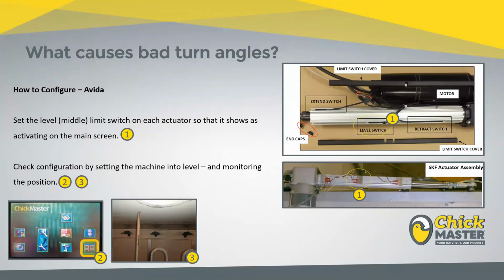Now, your extend and retract limit switches are very easy to set. They all come with little grub screws. You just loosen up those grub screws and then slide them up and down the shaft of that actuator. Those reed switches are triggered by a magnet, much like the bottom turning system, that's built into the actuator itself, and it's just a little rare earth magnet. And changing the turn angle is as simple as moving those reed switches either closer to the end to increase the turn angles, or closer to the middle to reduce them.